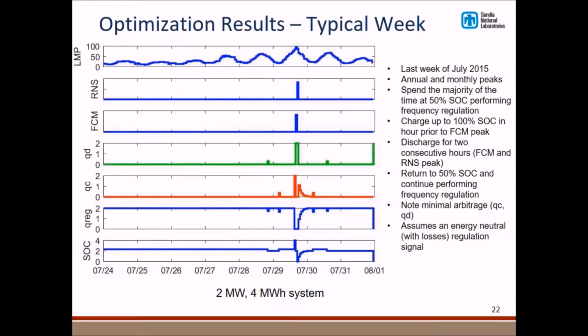This slide shows the optimization results for a typical week, the last week of July 2015, which happened to be when they had the monthly peak and the annual peak. If you go down to the last chart, the state of charge, you'll see you spend most of your time at roughly 50% state of charge. Q-reg, the second chart from the bottom, is the amount you're bidding in the regulation market, which is 2 megawatts, your full capacity. So the optimal policy is pretty much to do regulation all the time, and then right before the peaks are expected, you stop doing regulation and charge up to 100% state of charge.